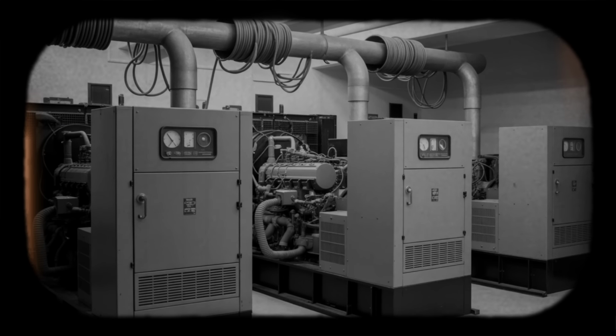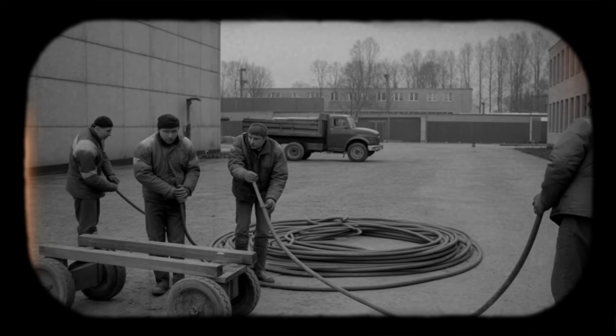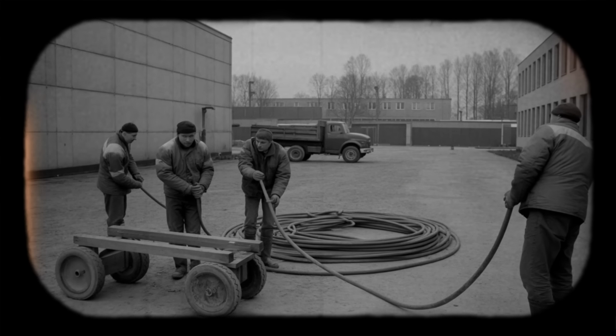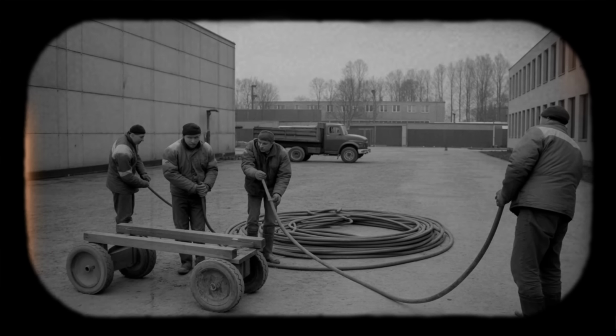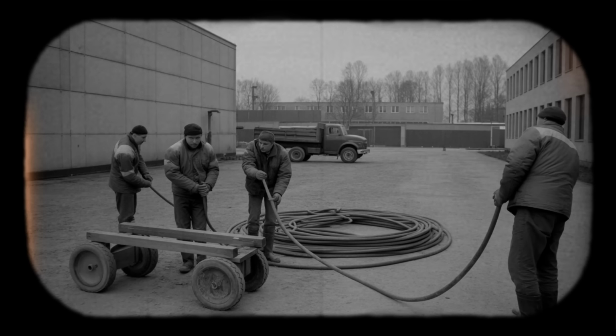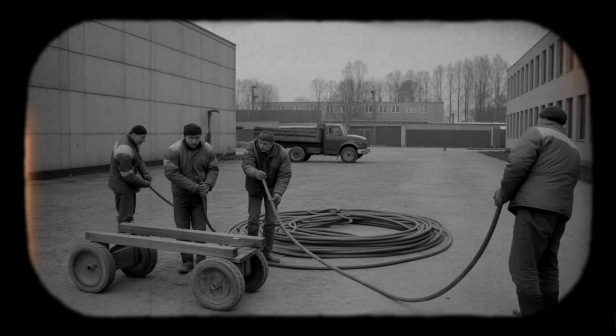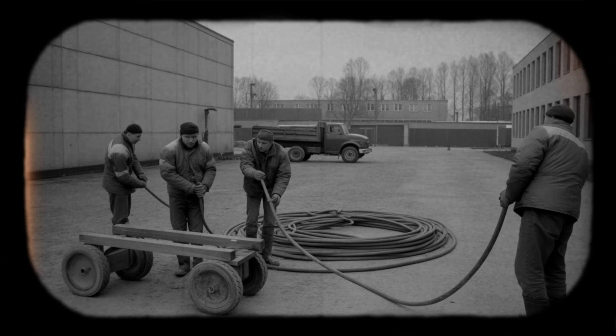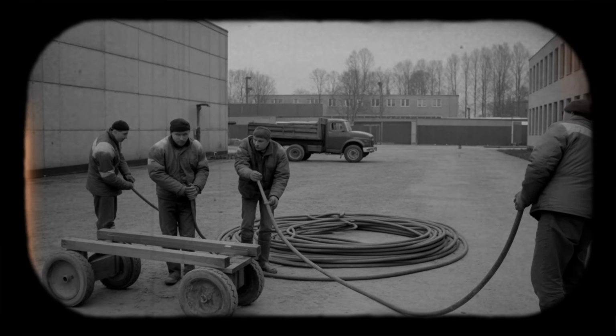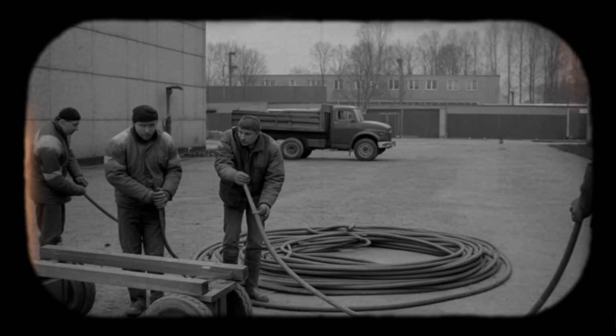Design reviews assumed breakers would function. This one did not. At this stage, the nuclear safety significance remained unclear. A 6 kV backup system, formerly not required at power, was on fire. Operators had not yet seen the consequences ripple through other systems. They did not yet know that this single cable fault, in a system considered non-essential, would remove almost every path to cooling the reactor core. The paradox was already forming.